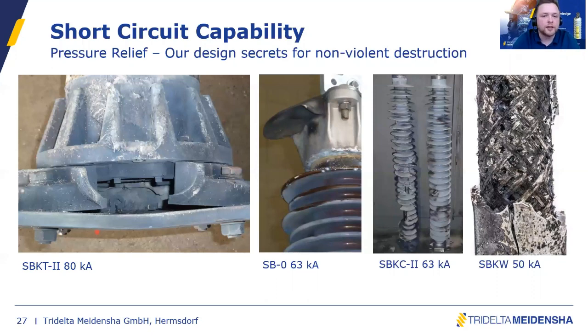What is impressive on the left picture is that this bent plate we see on the low side of the surge arrester is a 20 millimeter thick steel plate. So there is much force provided by this inner pressure, just to explain how much energy, how much pressure is created inside the housing. And we see the two pictures on the right side, SBKC and SBKW. There the pressure relief works differently. We have a soft shell, which is easy to destroy. You only have to make sure that the inner parts don't fly out, like the MOV blocks or aluminium parts. So those designs provide a very strong, very rigid housing, protecting inner parts from coming out, but also providing a pressure relief by a kind of membrane behavior.